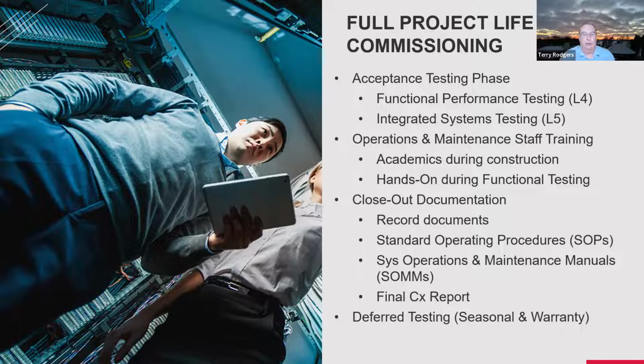Then you get to the acceptance testing phase where the infrastructure is built, it's energized, started up by the vendors and declared ready for operation. That's where the commissioning agent comes in and does the functional performance testing of all the equipment and the systems. And then that usually culminates in an integrated systems test, also called a pull the plug test in some venues, where you literally hit the building with the worst anomalies that it's programmed to withstand, and see that the building automation systems and all the other systems react accordingly and protect the site, or at least restore it once power is restored, et cetera.